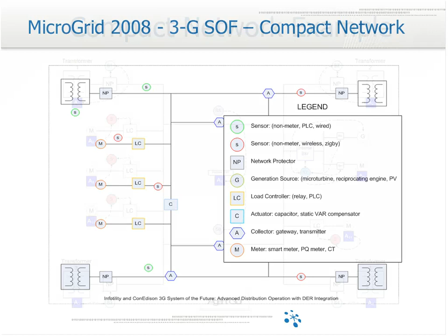One example was the same compact network, now with a backup generator. You've got transformers modeled by an agent, and the agents can look at simple things like the temperature profile over the past hour, where it's going, whether it's overheating. One example: the transformers are overheating. It's a very hot day at 4 in the afternoon in the middle of summer in Manhattan, and the old school way was to send a fire truck out and spray the transformer.